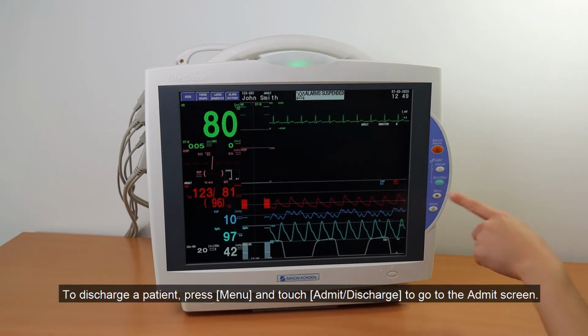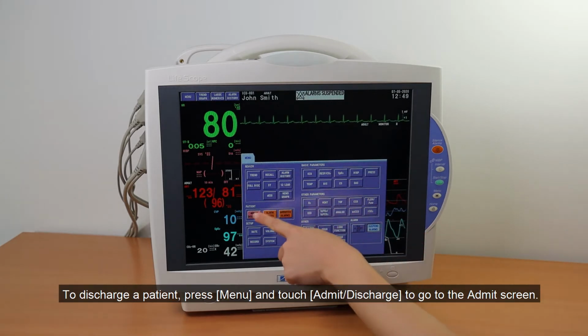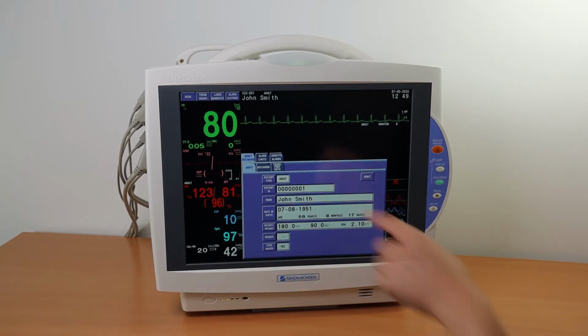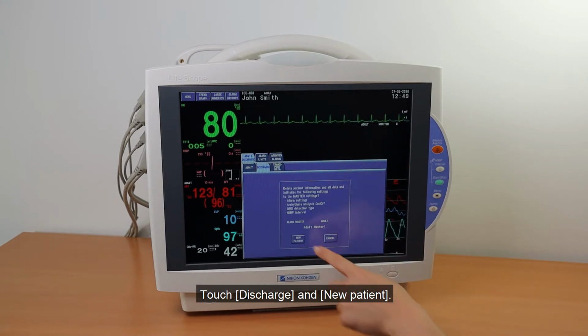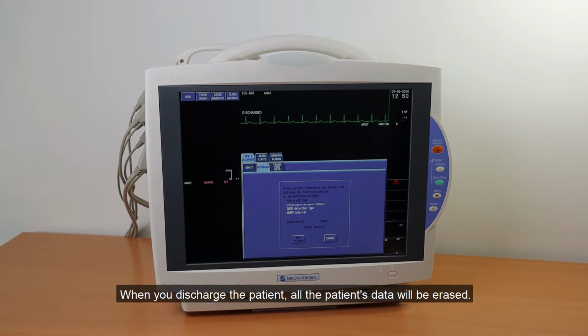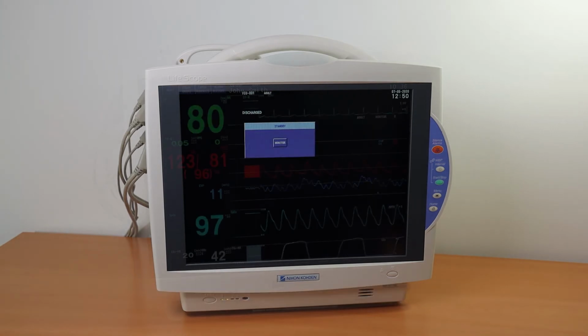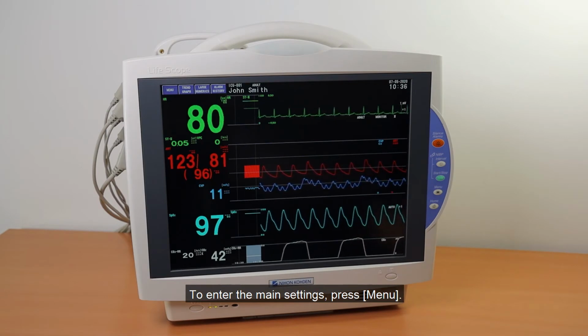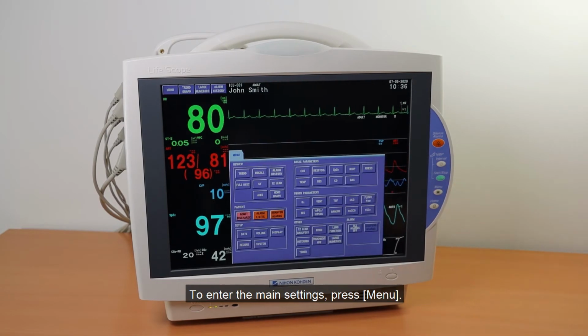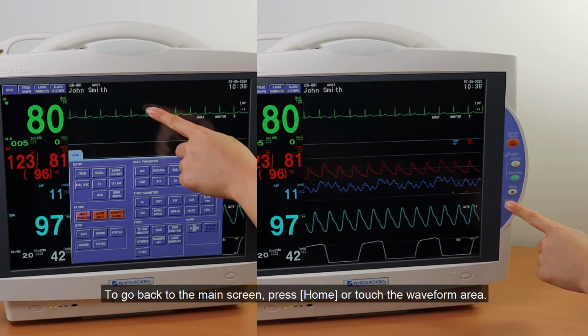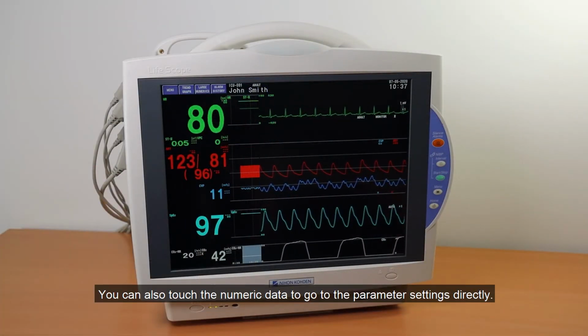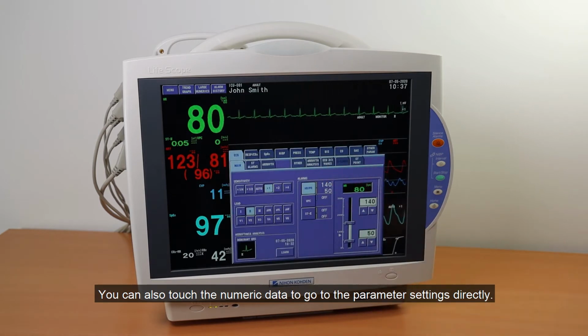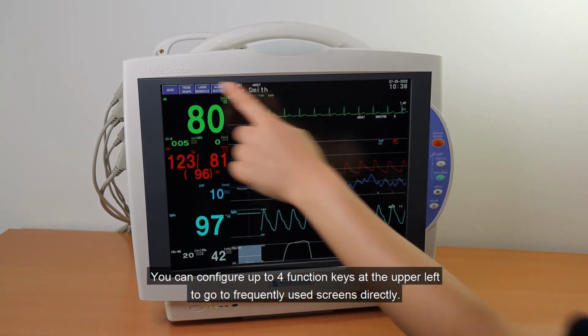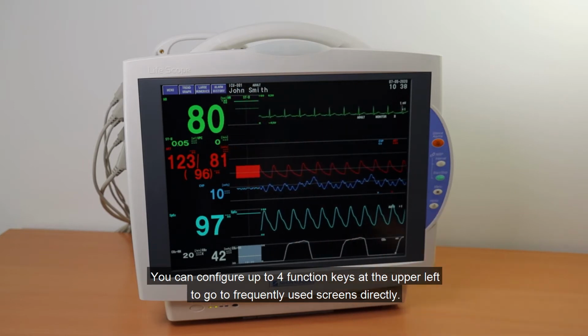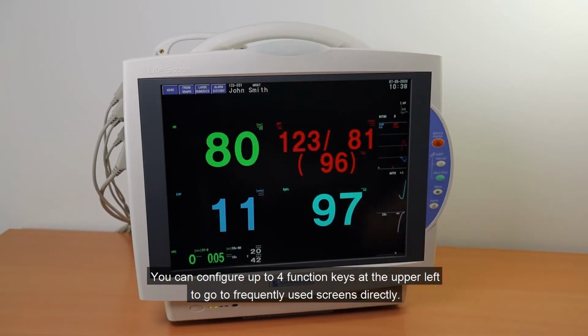The bedside monitor has now started monitoring the patient. To discharge a patient, press Menu and touch Admit Discharge to go to the Admit screen. Touch Discharge and New Patient. When you discharge the patient, all the patient's data will be erased. To enter the main settings, press Menu. To go back to the main screen, press Home or touch the waveform area. You can also touch the numeric data to go to the parameter settings directly. You can configure up to 4 function keys at the upper left to go to frequently used screens directly.